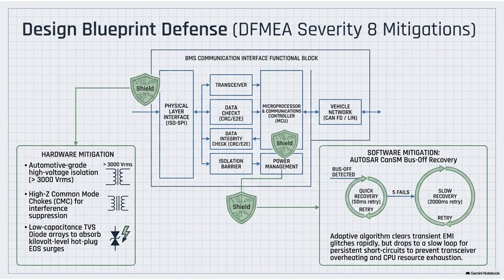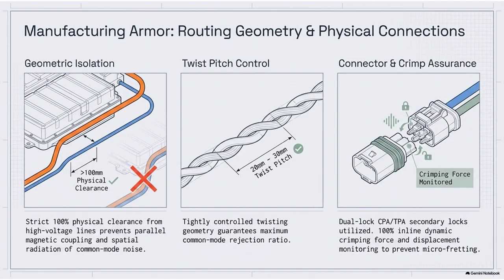So it tries again. It will try this rapid 50-millisecond quick recovery loop up to 5 times in rapid succession. If it fails all 5 times, the software's logic concludes that the problem is not a temporary phantom, it is a severe physical reality. Okay. And so it shifts into the second stage, slow recovery. And what does slow recovery do? It drastically slows down the retry attempts. Instead of trying every 50 milliseconds, it waits a full 2,000 milliseconds, 2 entire seconds, before attempting to reconnect again.